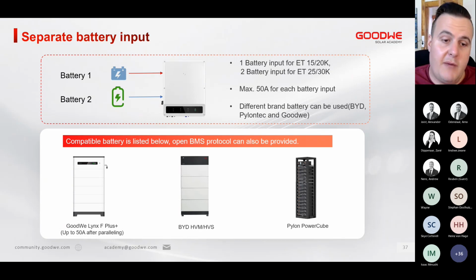But the larger ones have two battery inputs. So if your customer already, for interest's sake, has an ET inverter installed and they would rather upgrade to a 25 or a 30 kilowatt, you can install that now, put the battery that you already have on the one input and a new battery on the second input, and they are completely split in that sense. So it gives you a lot more flexibility. If availability is a problem on certain batteries, then you can put one battery bank on the one side and a different battery bank on the other side.